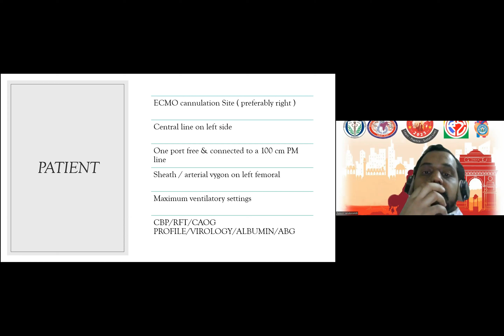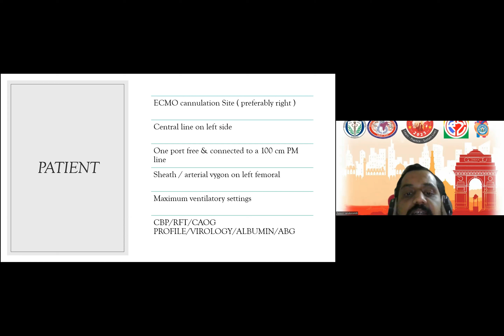You always keep one port free for giving drugs during your initiation part, and that one port should have a 100 centimeter extension line, and that one should be handled by a separate person. So why should there be a sheath or an arterial line on the left femoral? It's a protective measure. In case a cardiac arrest or a cardiac tamponade happens, my center always advocates having an arterial line on the left side, so that in case of a cardiac arrest, once CPR is going on, they can always convert from VV to VA ECMO. So that's the advantage of having it. And at the same time, you can also use it for monitoring the arterial line pressures.